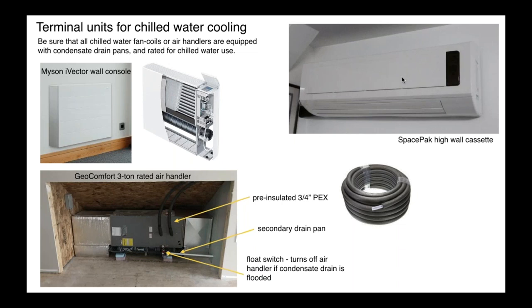Here's a high wall air handler. It's virtually identical in appearance and concept to a ductless mini split. The difference is it's a water coil versus a refrigerant coil. It turns on with a remote. The louvers down here oscillate up and down just like with a ductless mini split. You're just using chill water.